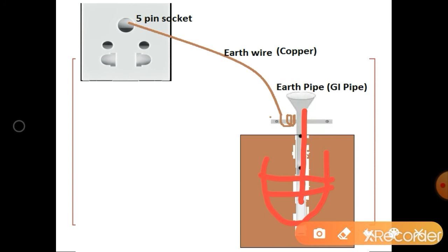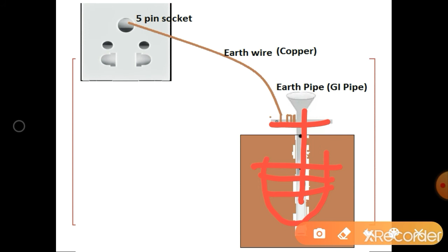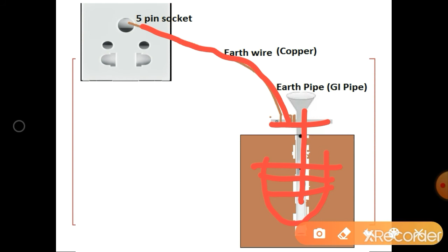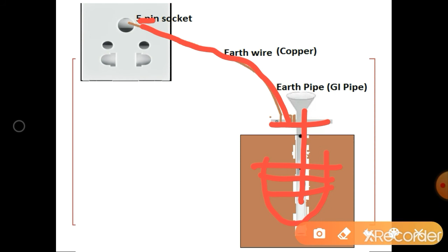Now let's look at this diagram clearly. Here the pit is excavated to 3 meter depth, and the galvanized iron pipe is placed. The gap is filled with layers of charcoal, sand and salt. This is the clamp, where the earth wire is connected. The other end of the earth wire is connected to the earth pin of the 5 pin socket or 3 pin socket.